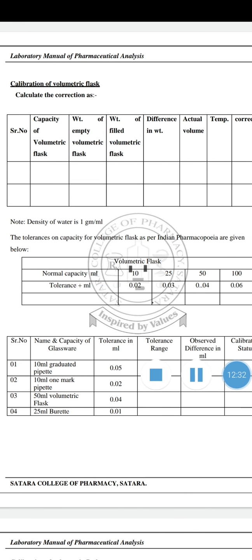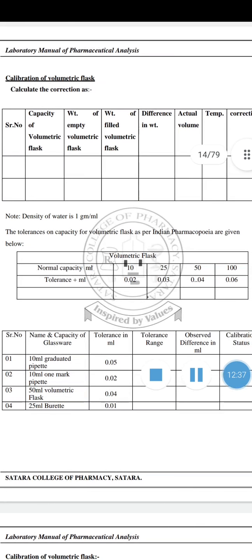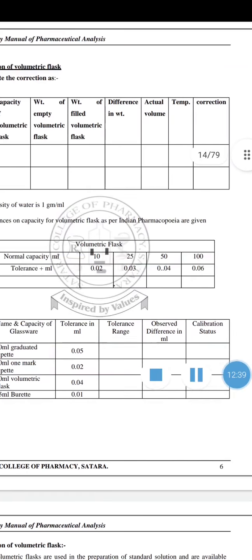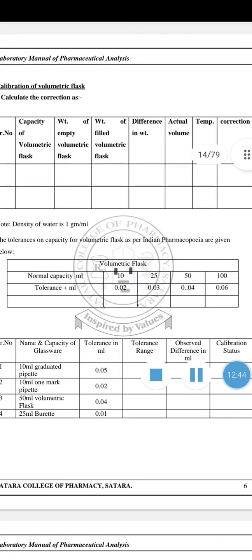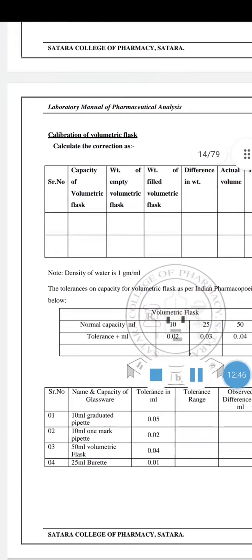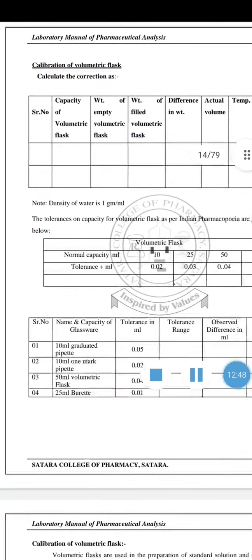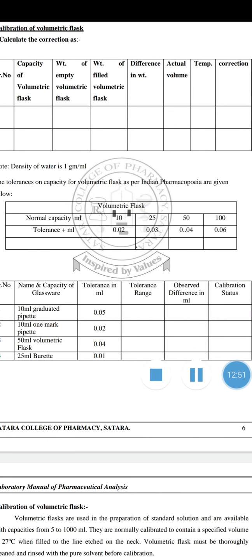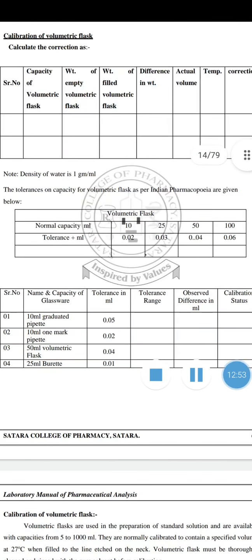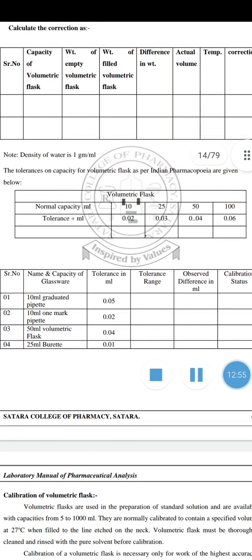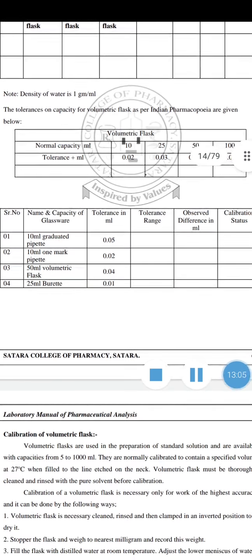This is the observation table. Calibration of the volumetric flask: there is the capacity of the volumetric flask, then weight of empty volumetric flask, weight of filled volumetric flask, then difference in weight, then actual volume and temperature and corrections. Then there is the tolerance on capacity for volumetric flasks as per the Indian Pharmacopoeia, given below. Nominal capacity 10 ml, 25, 50 and 100 ml. Tolerance plus or minus ml is 0.02, 0.03, 0.04, 0.06.